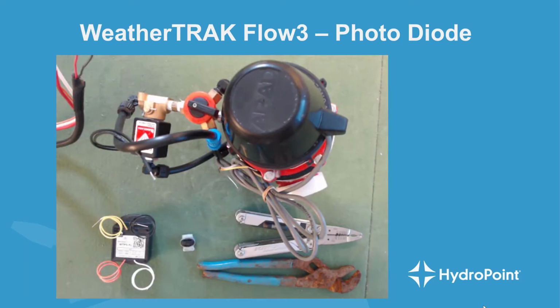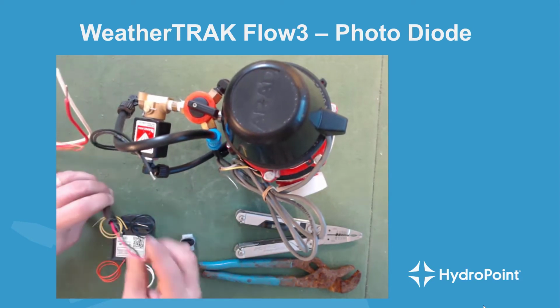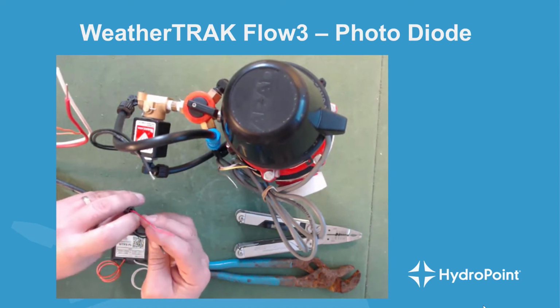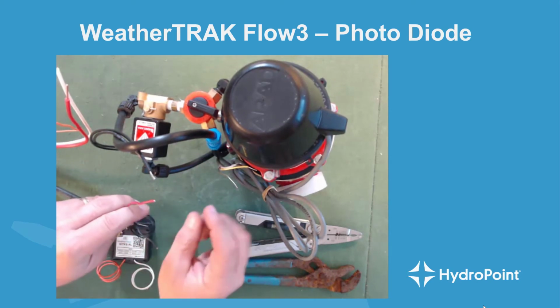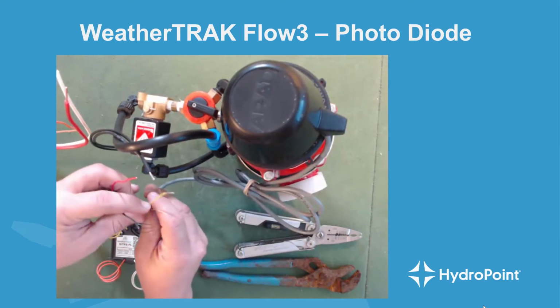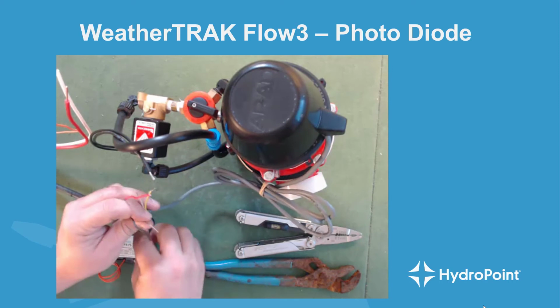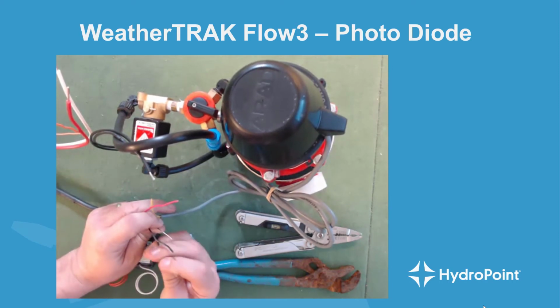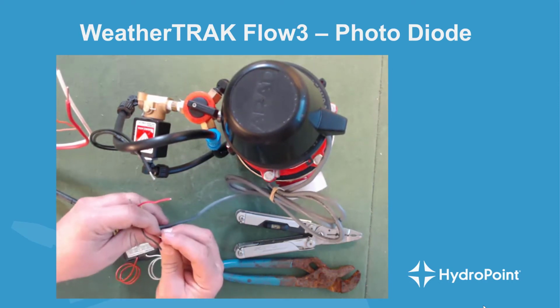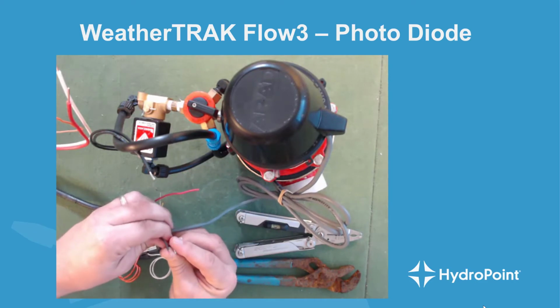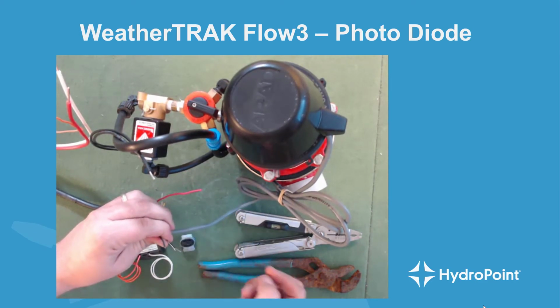And once we've found it on the wiring diagram, we go into our valve box and find those three same components. So we start with our shielded wire coming from our controller, find the black shielded wire, find the bare copper from the flow sensor, and find the black wire coming from the power supply. It's these three wires that we want to connect together.